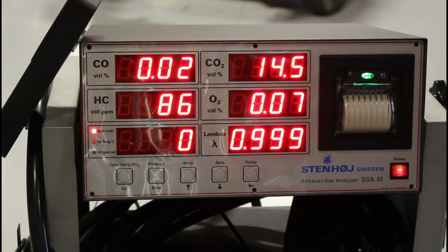And as your CO gets warmer, it'll go from 0.05 to 0.5%. Your CO2 is 12 to 14% when it's cold, and as it warms up it'll go from 14 to 15.5%. It's measured as a percentage again. Your O2, which is your oxygen, is 1 to 3% when it's cold. When it's warm, it's 0 to 1% as it warms up. Now, lambda. It is 0.9 to 1.1 when it's cold, and 0.97 to 1.03.